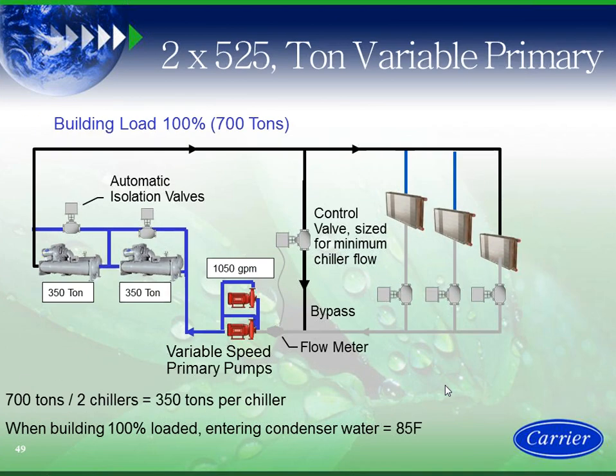Okay. Here is my diagram of my 2 525 ton machines and a variable primary load. Now they're going to run at 350 tons each. Now, the benefit to the 23XRV is that I can oversize it and not take a penalty on efficiency. Okay? However, you cannot oversize a centrifugal and not take a penalty on efficiency. Because in order for me to size a centrifugal, I have to size the wheel to handle the mass flow to get the tonnage. If I'm oversizing my wheel, that means when I'm not operating at that optimal point, I'm running less efficient. So the 23XRV, I could actually run it at reduced load at as good or better efficiencies than the design. So I could run it at 525 tons and have good kW per ton, and I could also run it at 350 tons and have it at good kW per ton.